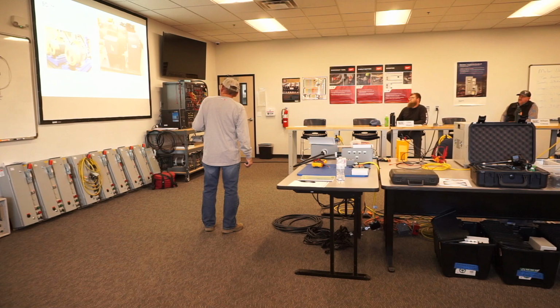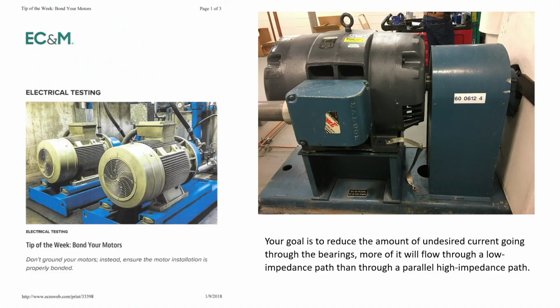As you can see, that braided strap, and you can buy them in separate lengths. This outfit in Dallas at the hospital put these braided straps on if I go out to check it out. They got them bolted onto a painted surface. How much resistance do you suppose that painted surface has? Well, you know, paint's a resistor. I said, sand the paint off. You're trying to provide a low impedance path. You land it on a painted surface, an insulator, you haven't accomplished anything. You have to do this so that it works.